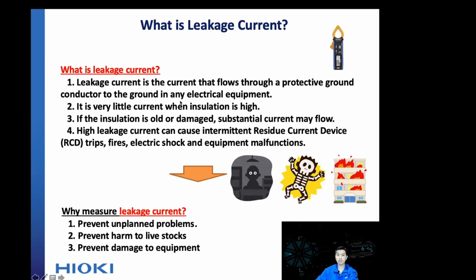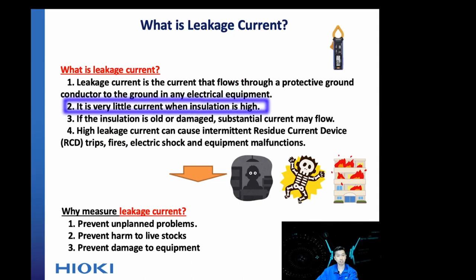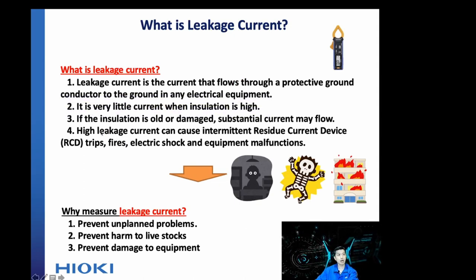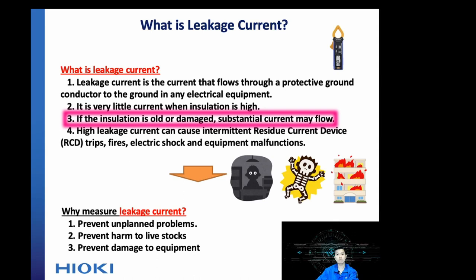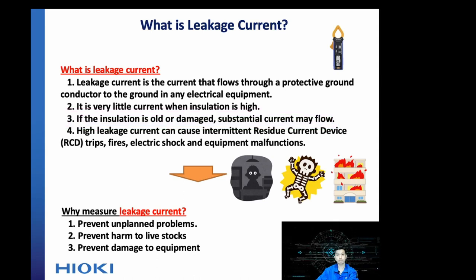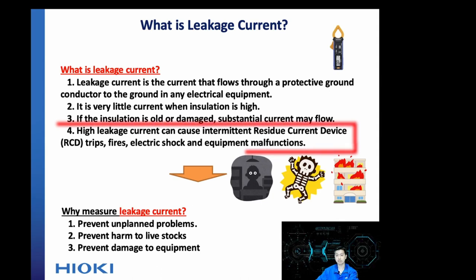Now, the second cause of leakage current: if the insulation of the cable is high, then there will be very small leakage current. However, if the insulation is weak or damaged, substantial leakage current may flow. Ultimately, this high leakage current may cause intermittent tripping on the residual current devices.